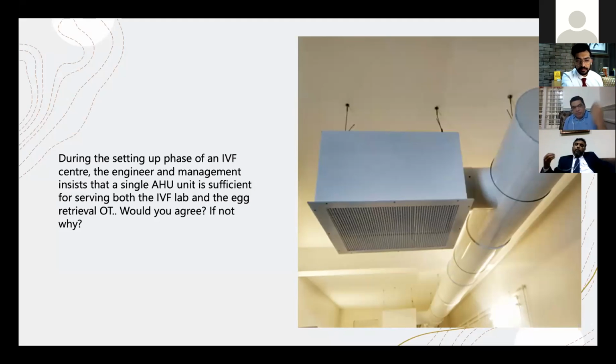See, there was some discussion about it in some of the interactive meetings. If the engineering team can design an AHU which can cater to the needs of both sides, it is okay to go with the same AHU. But with the kind of expertise that we get in our country, I think it is always better to go with a separate, dedicated AHU for the IVF laboratory, so that you won't be mixing the pollutants or the disinfectant coming from the OT. Nowadays, if you don't have a proper pressurizing system, you can even get high VOC when the anesthetic gas is being used at the egg retrieval time. So ideally it should go with separate AHUs.